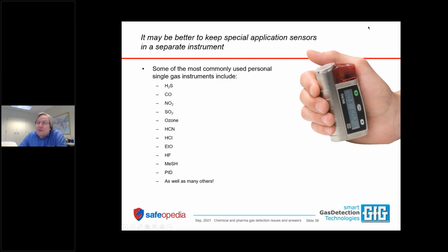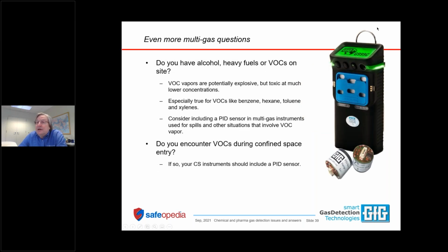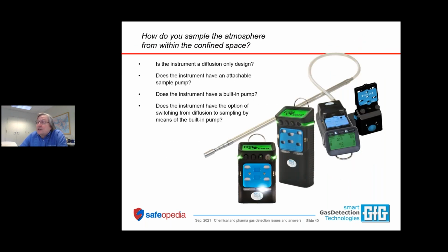If you have an instrument or a sensor that just takes a little more work, harder to calibrate, more expensive to calibrate, more expensive to do a bump test on, then keeping it in a separate instrument which you use only when you need to use it makes a lot of good sense. Again, watch out for alcohols in big pharma. I really urge you to take a look at using an infrared sensor if you are needing to measure methanol in particular or other alcohols.